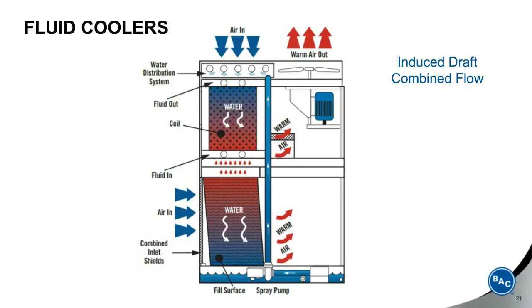And that allows you to, number one, reduce the amount of coil you need, which lowers the weight of the unit, but it also can improve the heat transfer ability of the coil itself such that it's greater than what a traditional coil-only design would be. And you can achieve closer approaches at lower fan horsepowers. So this design has real advantages, and the last one being that the heat transfer in the coil area is actually primarily sensible heat transfer, not evaporative heat transfer.